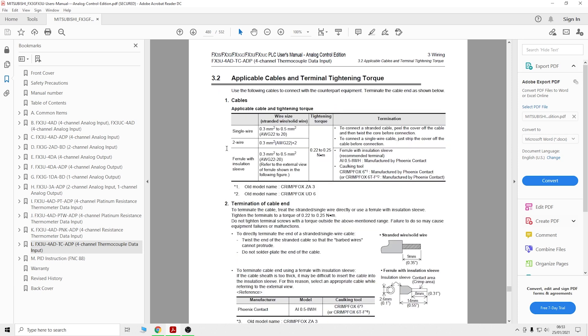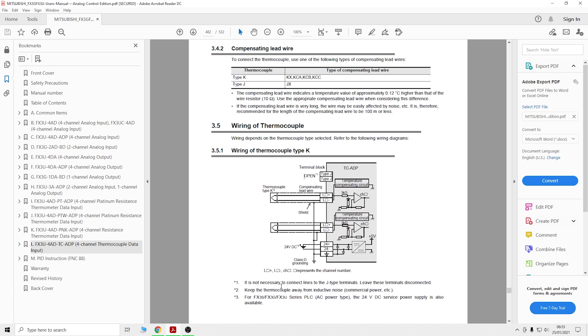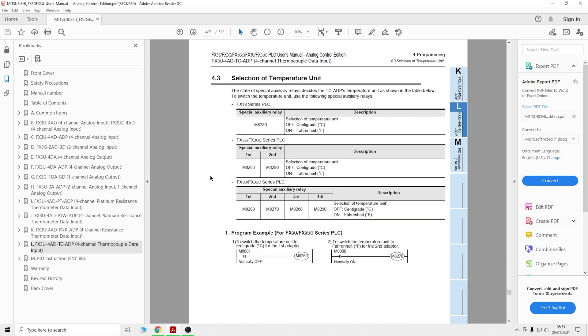Looking at the wiring section and more specifically the thermocouple wiring - here you can see the wiring of the K thermocouple channel versus the J type. For K type the J terminal has to be open, and the manual even states it is not necessary to connect the line to the J-type terminal - leave these terminals disconnected. So make sure that is the case for your K type thermocouple.